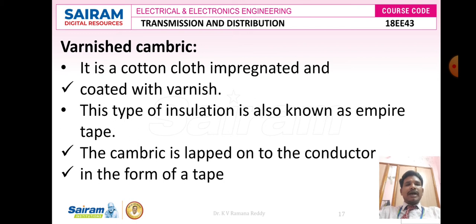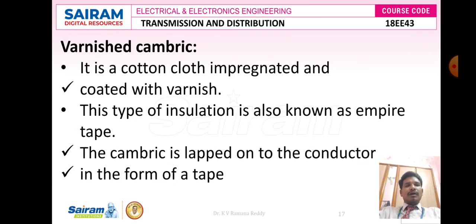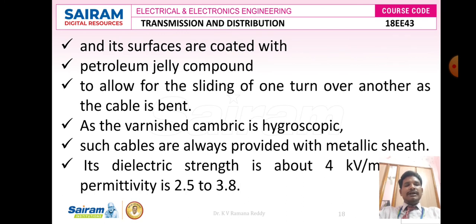The next insulating material is varnish cambric, which is simply a cotton cloth impregnated and coated with varnish. This type of insulation is also known as empire tape. The cambric is lapped onto the conductor in the form of a tape, and its surfaces are coated with petroleum jelly compound to allow sliding of one turn over another as the cable is bent. Like impregnated paper, varnish cambric is also hygroscopic, so these cables are always provided with a metallic sheath. The dielectric strength for varnish cambric is about 4 kV/mm and its relative permittivity εr is 2.5 to 3.8.